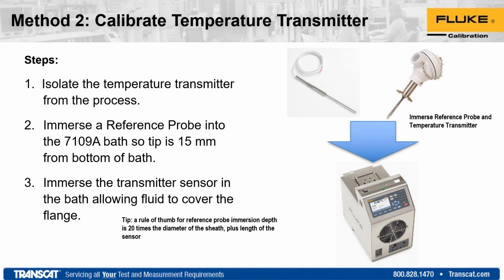And then too, just in general, a good rule of thumb on any sensor testing is usually 20 times the diameter plus the length of the sensor. If you don't know the sensor length, or if it's a thermocouple, typically you can stick with just 20 times the diameter. So typically, if you run the math out, a 1/4 inch probe comes up to roughly 5.5 to 6 inches of immersion. What this does is, once you get that much immersion, you reduce what they call stem conduction, where your probe is conducting ambient air or heat sinking. It's usually more apparent if you're testing to very hot or very cold extremes, because then you've got this ambient metal piece acting as a cooling heat sink or a heating heat sink, depending on which direction you're going.